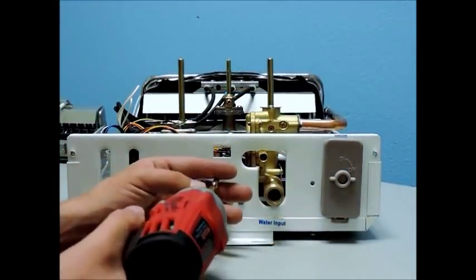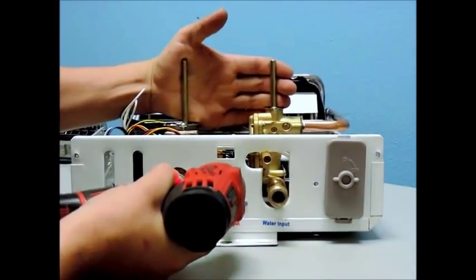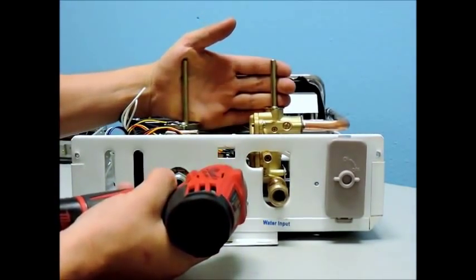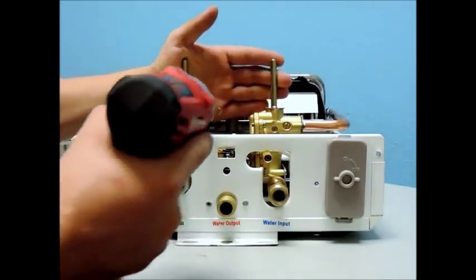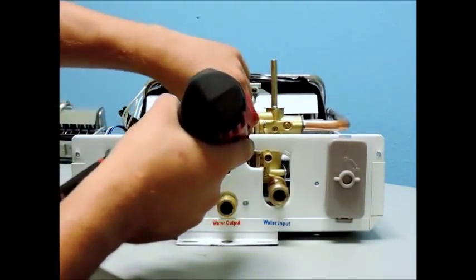Now, we want to start removing the burner assembly. There are two screws that secure the burner assembly to the brass water valve assembly. It is very important to start with the bottom screw that can be located through the access hole on the bottom of the case.